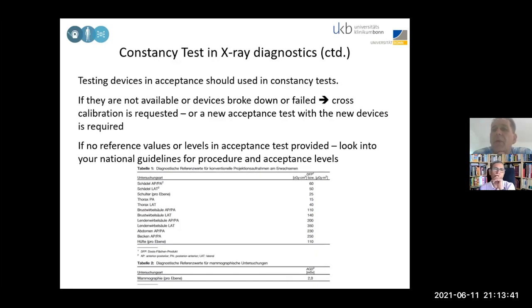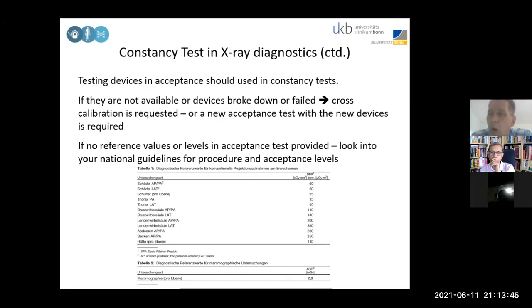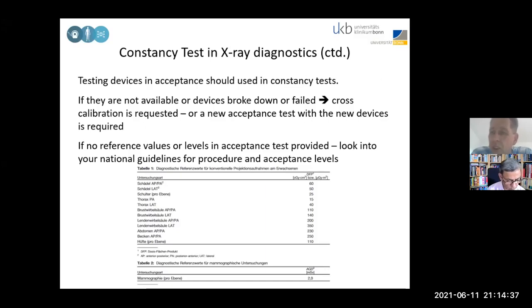There's another problem before you really start doing constancy checks: how are the acceptance test values, which are your basic values, measured? The problem is the equipment. The machine stays the same, but the equipment might be changed, because you did the acceptance test with the equipment from the vendor, and then you start doing the constancy check with your equipment. Usually you have a gap or an offset or some other values. In those cases, I recommend that you either do a cross calibration, so you measure with the vendor's equipment and with yours, and then you can cross-check the values, or you say that the acceptance test is done with your equipment and not with the vendor equipment.